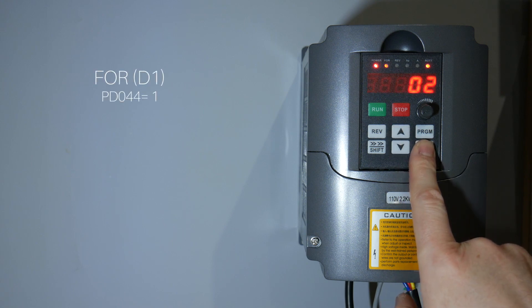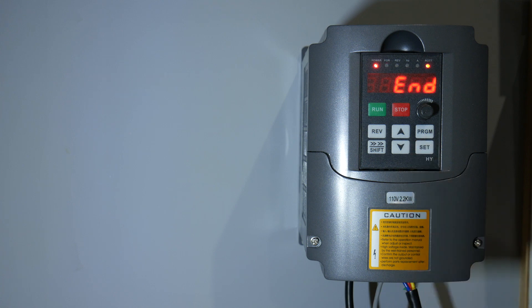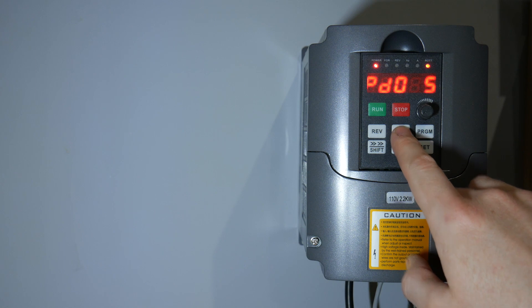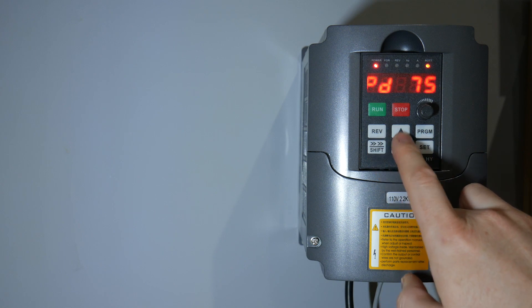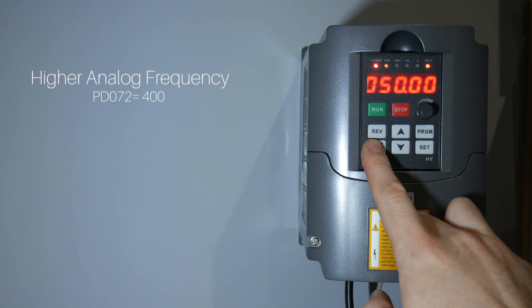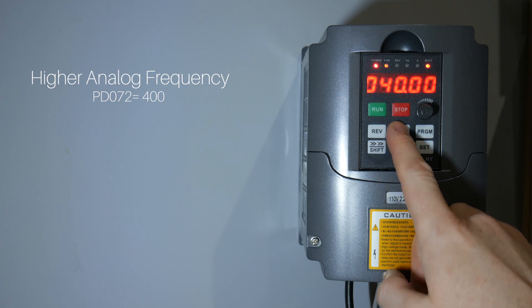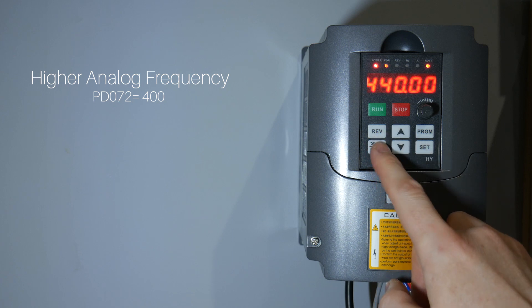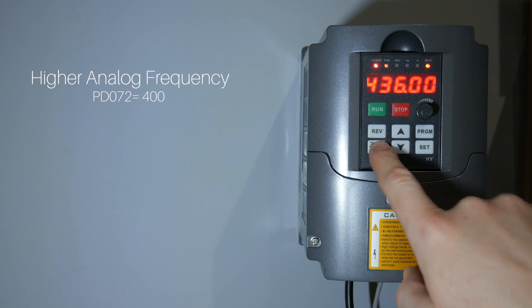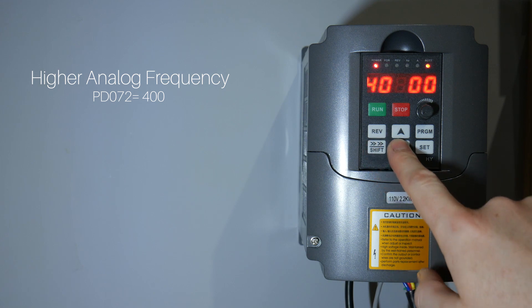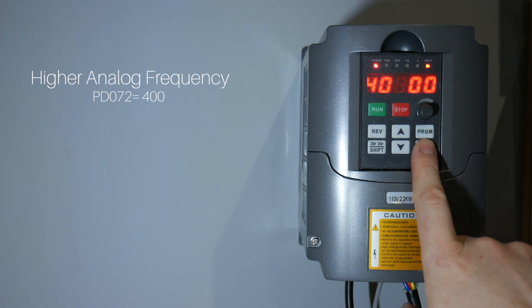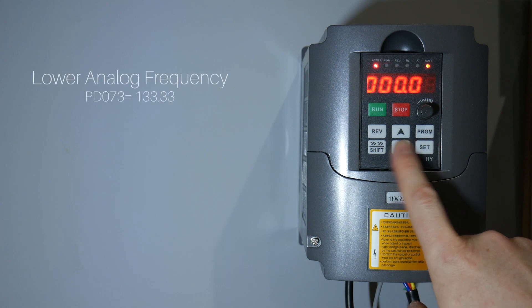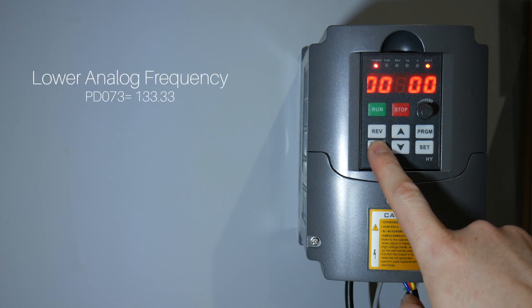Set the function for the D1 pin or FOR pin to 1 for run. Configure the higher analog frequency to 400 hertz. And configure the lower analog frequency to 133.33.